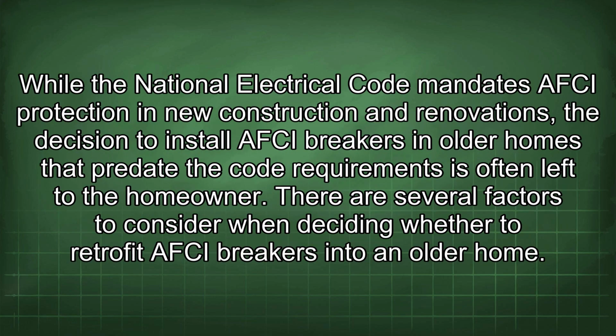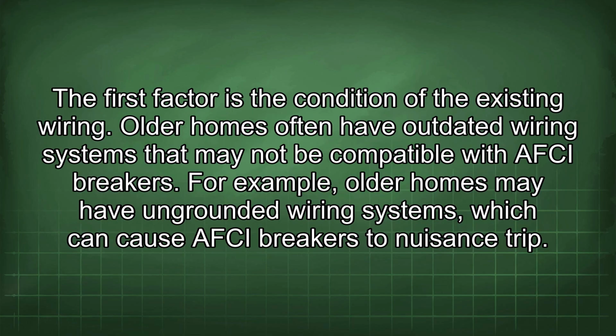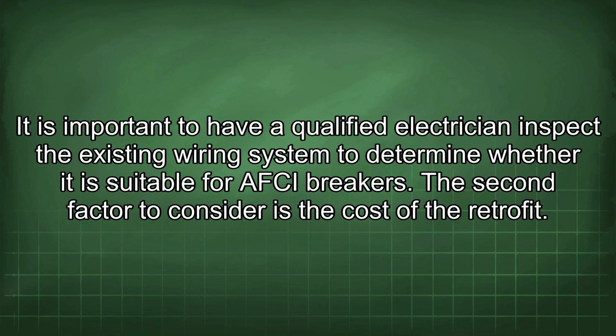While the National Electrical Code mandates AFCI protection in new construction and renovations, the decision to install AFCI breakers in older homes that predate the code requirements is often left to the homeowner. There are several factors to consider when deciding whether to retrofit AFCI breakers into an older home. The first factor is the condition of the existing wiring. Older homes often have outdated wiring systems that may not be compatible with AFCI breakers. For example, older homes may have ungrounded wiring systems, which can cause AFCI breakers to nuisance trip.